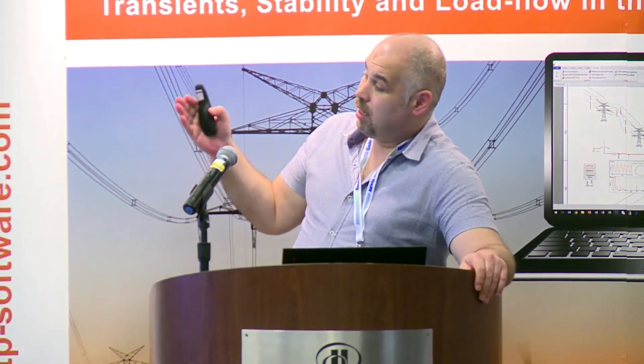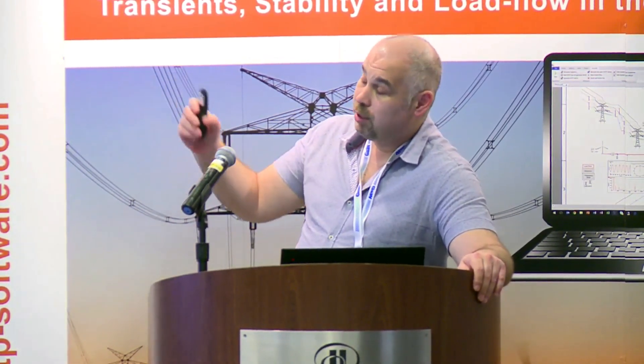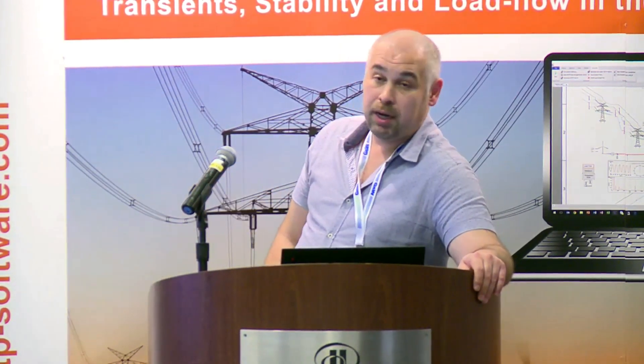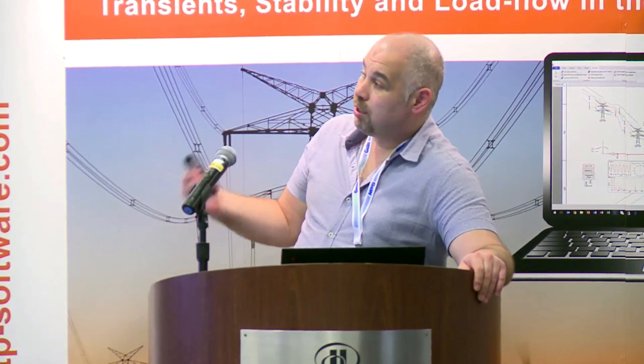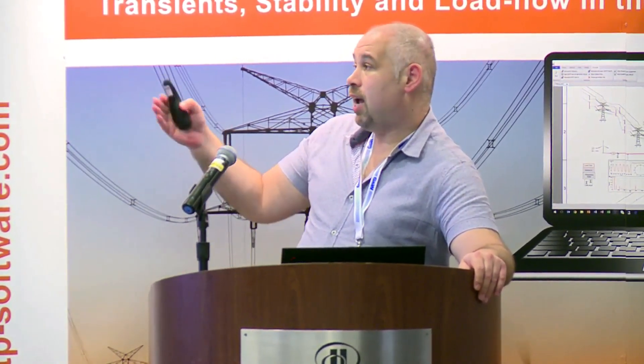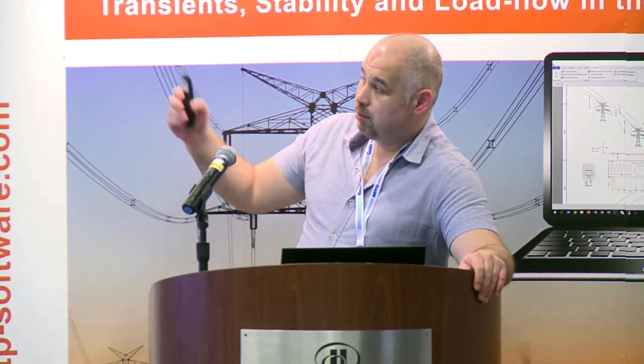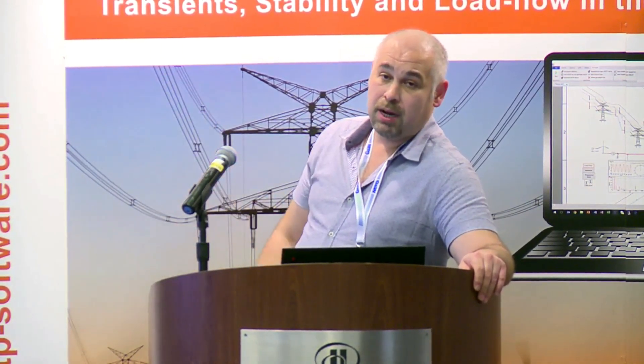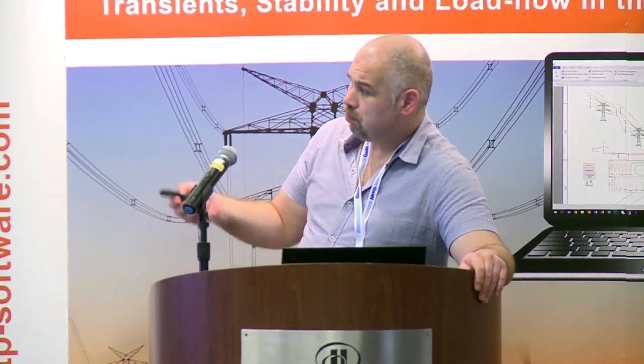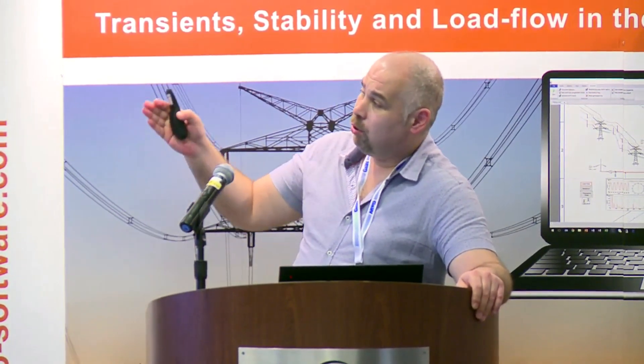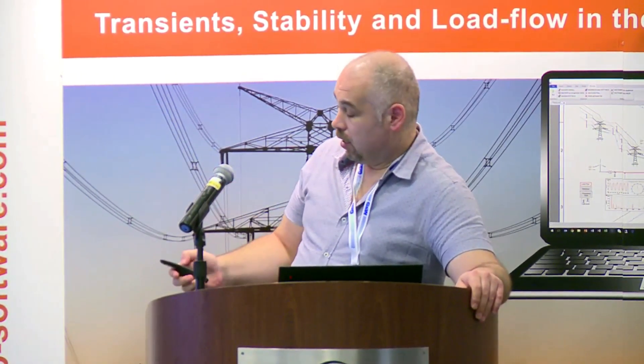The DFIG controls, especially the rotor side converter controls, have significant impact on the rotor resistance — the negative rotor resistance. We call this phenomenon subsynchronous control interaction (SSCI). It can take place with any power electronic-based equipment, not necessarily the DFIG. It is simply the interaction between the series capacitor and the control system. However, the mechanism is quite different, and many people also classify this problem under the induction generator effect.